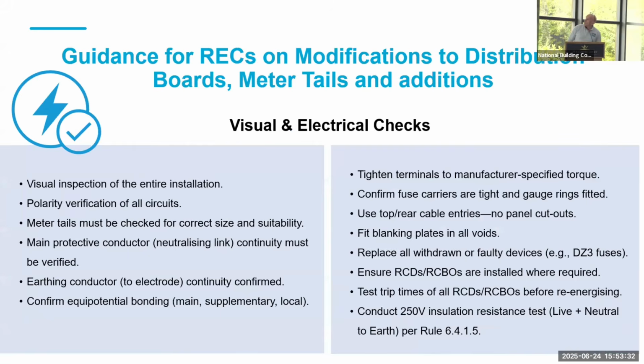6.4.1.5. Guidance for RECs on the modification, again, in distribution boards, the meter tails and additions. So visual and electrical checks. This is again transcribed from the wiring rules. So visual inspection on the entire installation. Polarity verification of all circuits. This is vital from what we've seen in the past, especially to do with electric car chargers being installed without undertaking all the previous points that I outlined. In certain cases, they reverse polarity. And what I mean by polarity is, you've live and neutral, and we need to have live and neutral in the correct places. But in certain cases where they've undertaken the alteration to meter tails to facilitate an EV car, they might have mixed up live and neutral on the existing. So we need them to check that in all cases.